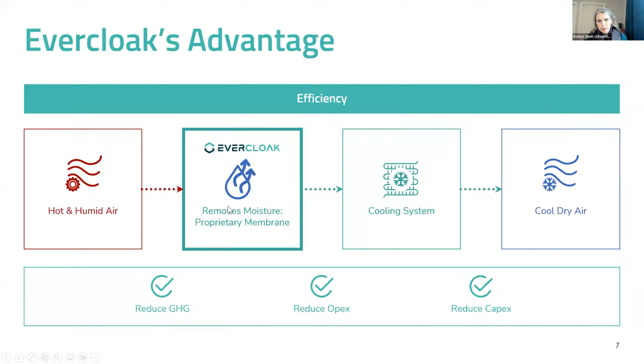We're able to essentially pull the moisture from the air while allowing the dry air to continue on. I like to say our membrane is an open door to water vapor and a closed door to gas or air. As a result of decoupling humidity from the cooling system, that system can be sized smaller, use less refrigerant, and have less OPEX and CAPEX, giving an opportunity for more efficient buildings and building cooling. Our technology can stand alone or be integrated into cooling technology. I'll talk a bit more about the stage we're at shortly.